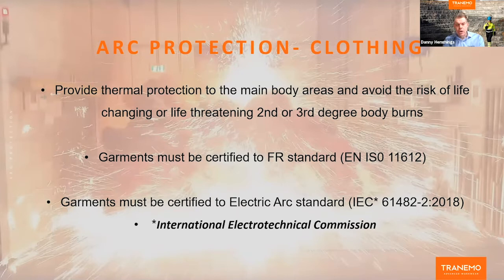The main thing we're trying to do with arc protective clothing is give that thermal protection to the core body areas. The focus being to reduce or eliminate the life-changing, life-threatening second or third degree body burns, as we touched on just before. So garments must meet the FR standard. Garments must also be certified to the electric arc standard, which is IEC 61482. IEC stands for International Electrotechnical Commission, so they are the international body that have created the standard specifically relating to electric arc.